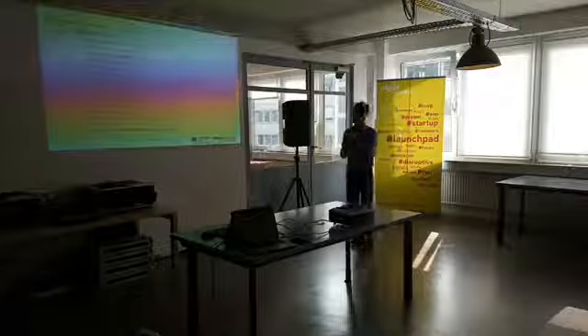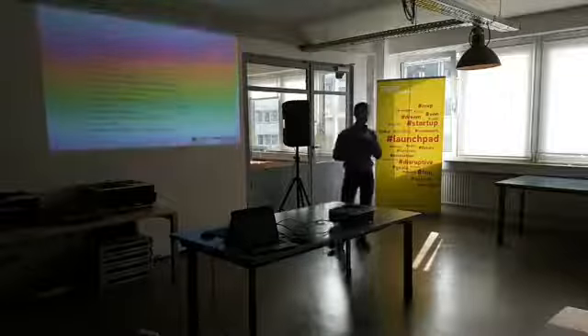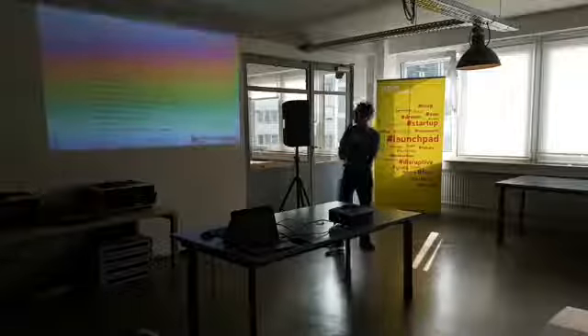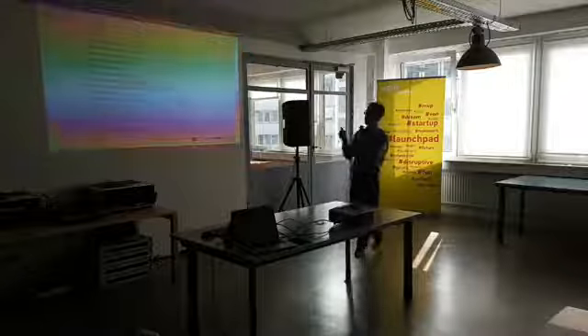Here are some indexes of how our system is performing. We expect an uncertainty in the order of 0.5% for the state estimation, and basically we run every second. We can keep real time because the time to read measurements is a quarter of a second, the time to run the estimation is very short, and then there's a little time to write into the database.